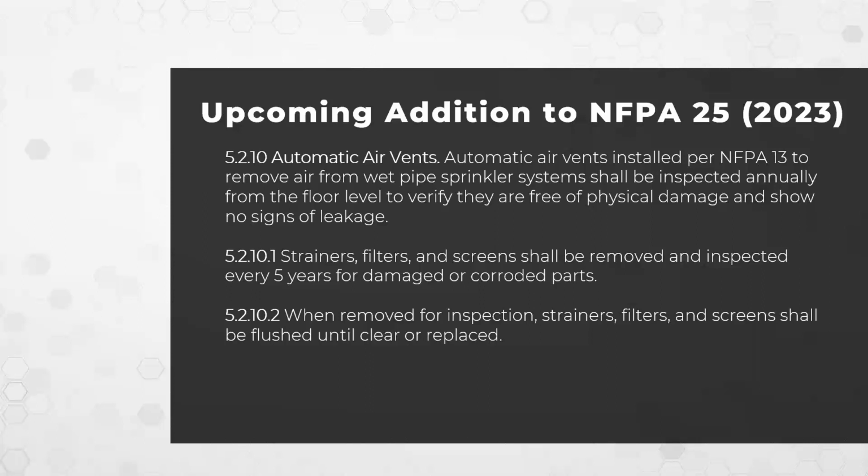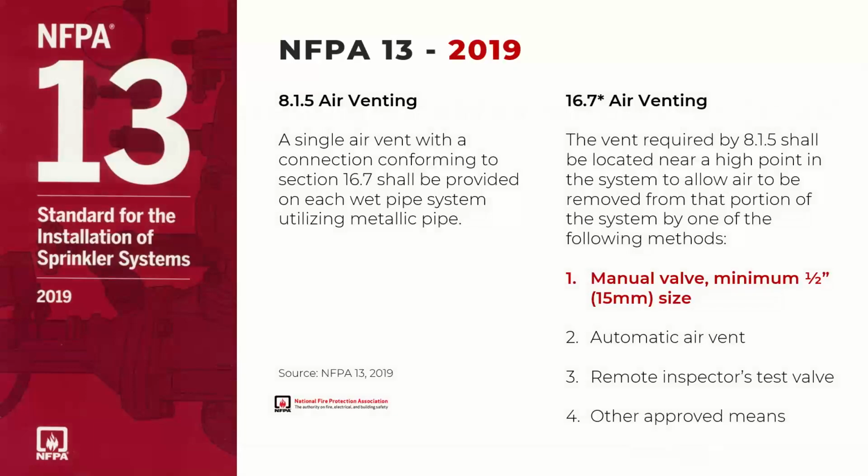It's the day after you put the system in, everything you're supposed to do to keep it in top shape for the lifespan of it. One of the issues is they are just recently adding language that you will be required to test and inspect your air vents. So that's something I bring to your note, especially if somebody was going to make a mistake and put it in an inconvenient location. Getting back to what the actual wording says, again, a single air vent near a high point.